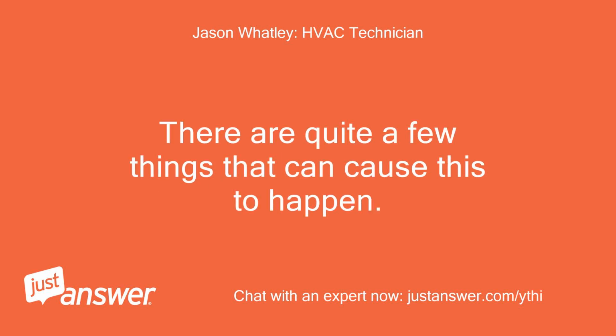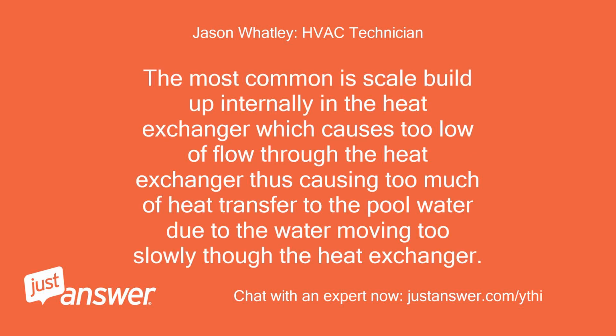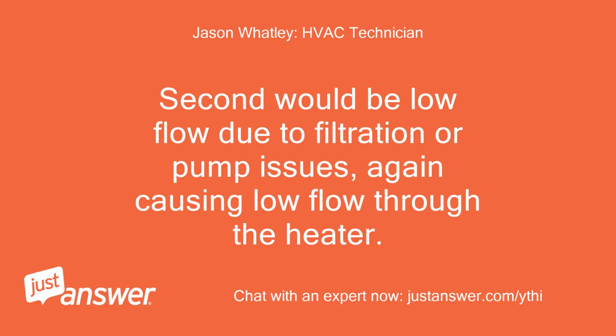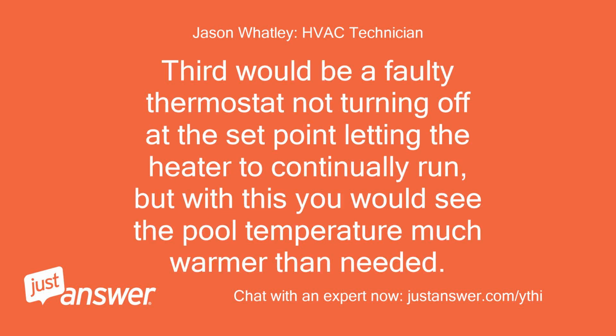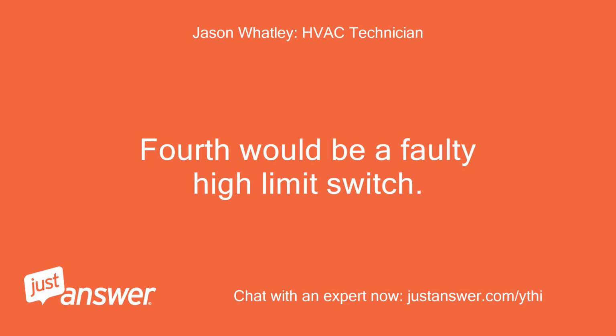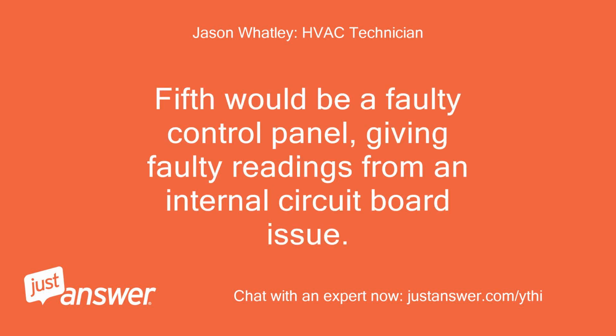There are quite a few things that can cause this to happen. The most common is scale buildup internally in the heat exchanger, which causes too low a flow through the heat exchanger, thus causing too much heat transfer to the pool water due to the water moving too slowly. Second would be low flow due to filtration or pump issues. Third would be a faulty thermostat not turning off at the set point, letting the heater continually run, but with this you would see the pool temperature much warmer than needed. Fourth would be a faulty high limit switch. Fifth would be a faulty control panel, giving faulty readings from an internal circuit board issue.